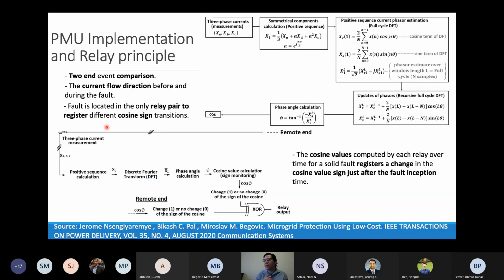Well, I'm testing the cosine sign. So basically, our model proposes measuring the current in the three-phase measurement, doing a positive sequence calculation, passing to a discrete Fourier transform. We use it in a phase angle calculation. Based on this, we obtain the cosine value for monitoring the sign, which means the direction of the current. And on the other end, we check whether it changed or not in order to trigger some relays.